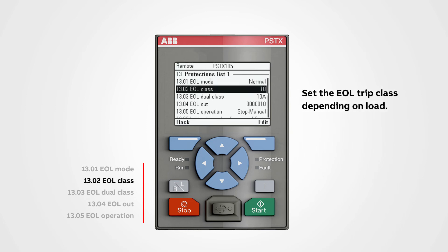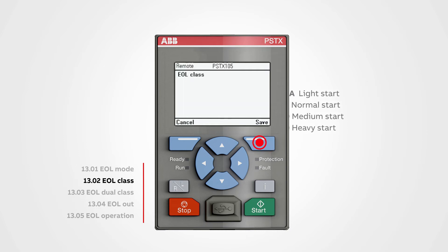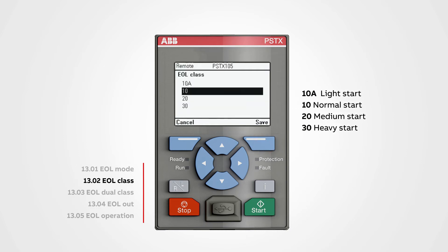EOL trip classes: set the EOL trip class depending on load — 10 for normal and 30 for heavy duty starts.